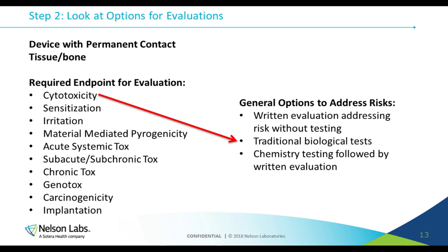So in this case, cytotoxicity was a required endpoint for evaluation. For cytotoxicity, we never really recommend doing anything other than the test. We found that regulators really like to see cytotoxicity testing as a way to screen for the unexpected, as a way to catch something that we're really not anticipating. And we've not had a lot of luck avoiding cytotoxicity testing without even attempting it at all. So for that endpoint, you really should plan on doing the traditional biological test.